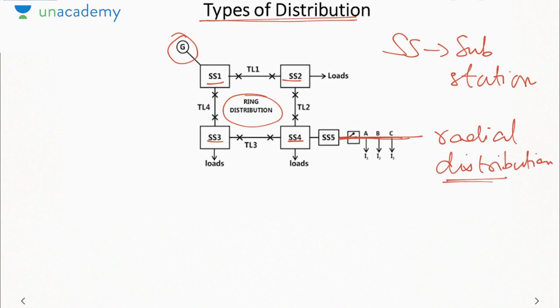Now what is the problem in radial distribution? As we saw in the previous two cases, when the source is fed from one end, as you move away from the source there will be voltage drop in the line, and voltage will go on reducing as you move farther away. So the load at the far end will always experience a lower voltage compared to a load connected near the source. That is why low voltages are observed in radial distribution.